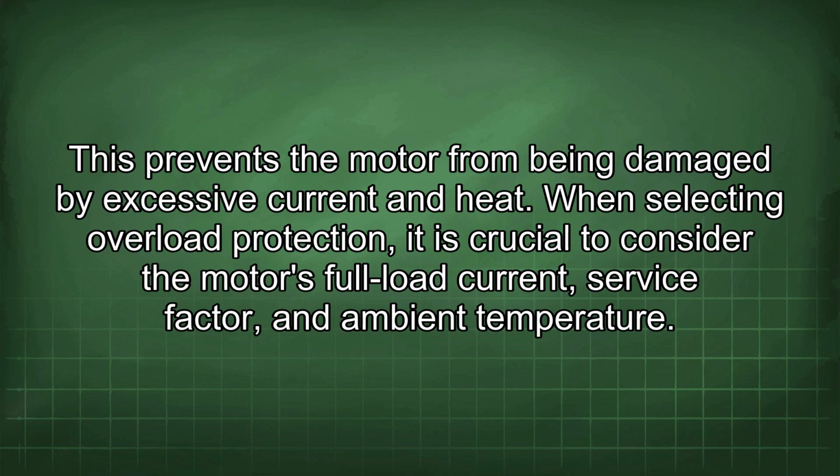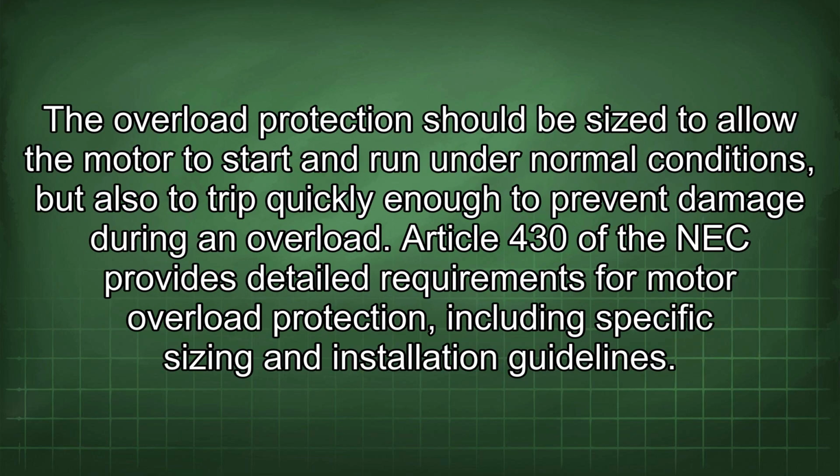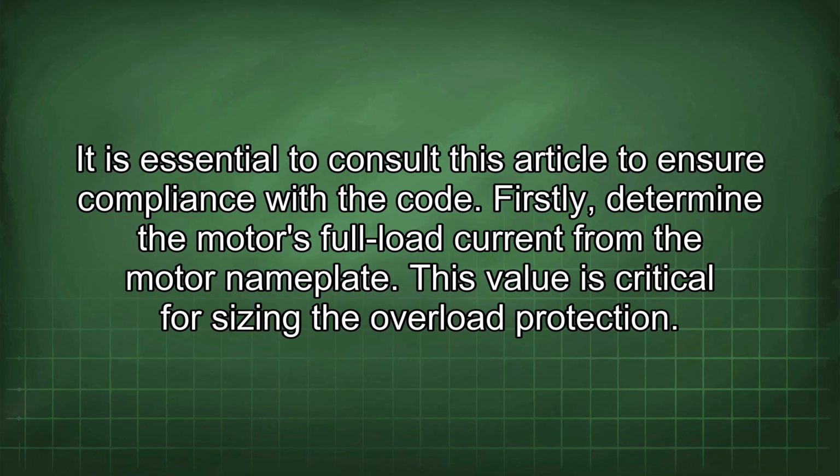When selecting overload protection, it is crucial to consider the motor's full load current, service factor, and ambient temperature. The overload protection should be sized to allow the motor to start and run under normal conditions, but also to trip quickly enough to prevent damage during an overload. Article 430 of the NEC provides detailed requirements for motor overload protection, including specific sizing and installation guidelines. It is essential to consult this article to ensure compliance with the code.